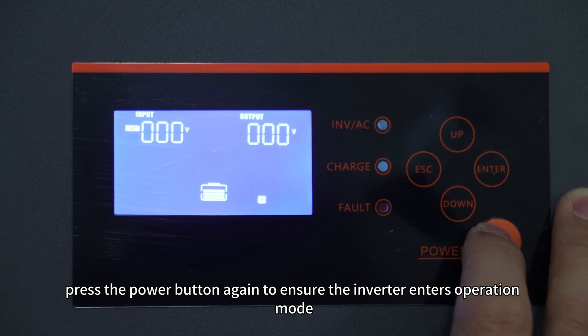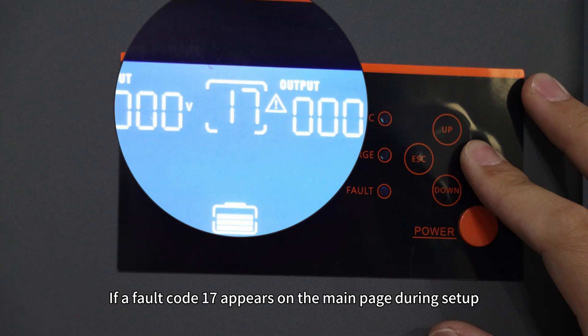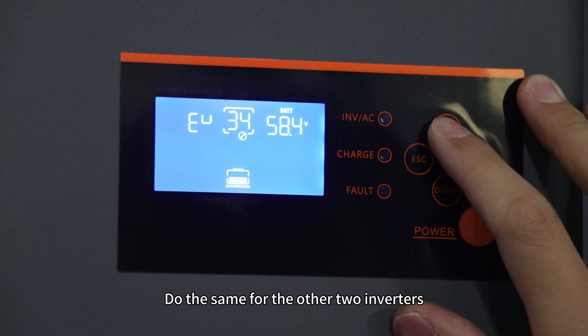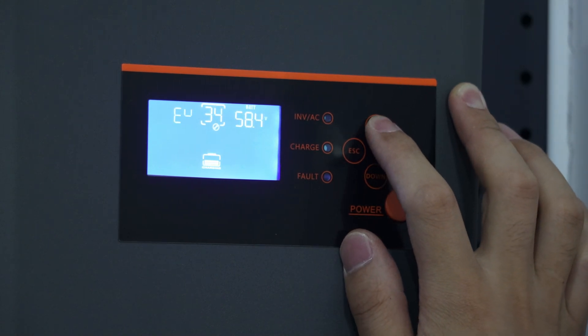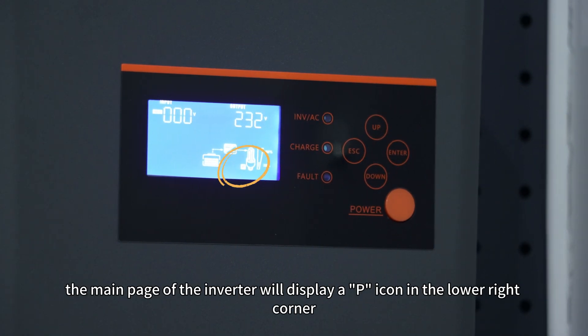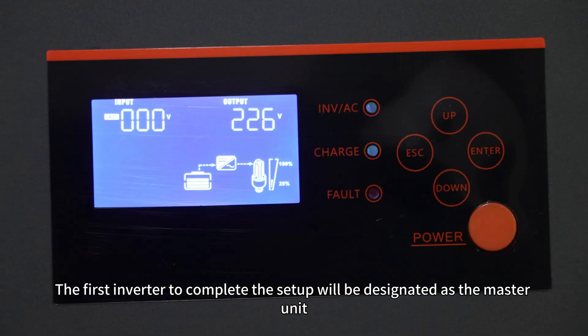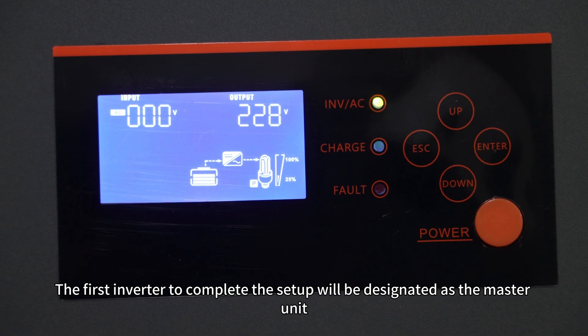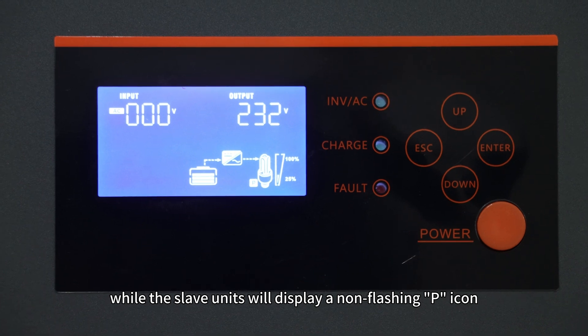Finally, press the power button again to ensure the inverter enters operation mode. If fault code 17 appears on the main page during setup, do not worry — it will disappear after setup is completed. Do the same for the other two inverters, setting item 28 to PAL. After the setup is done, the main page of the inverter will display a P icon in the lower right corner. The first inverter to complete the setup will be designated as the master unit with a flashing P icon, while the slave units will display a non-flashing P icon.